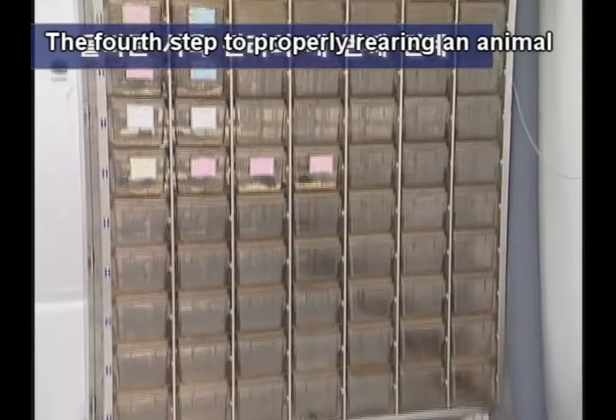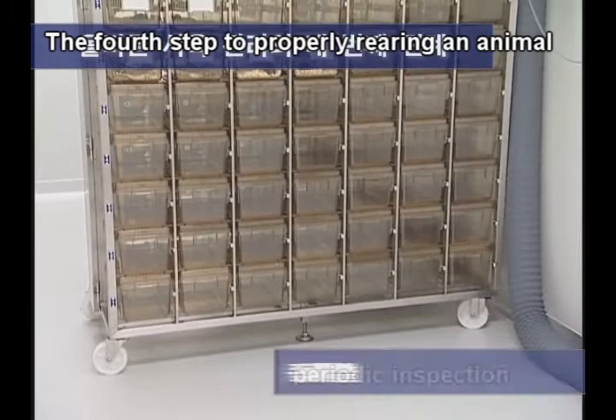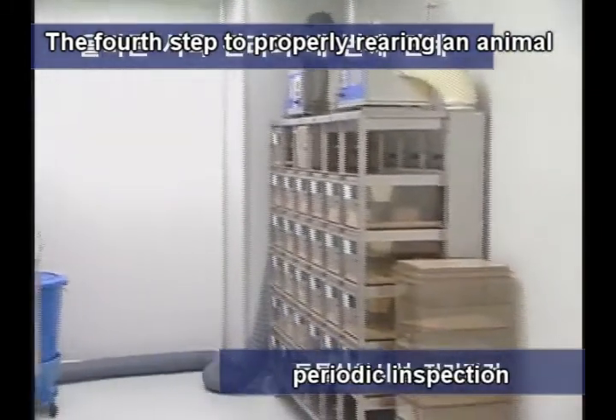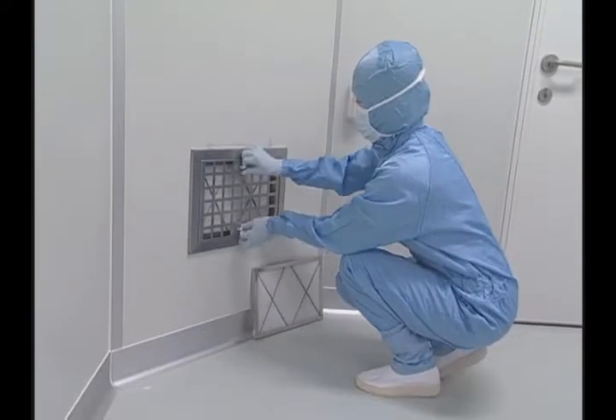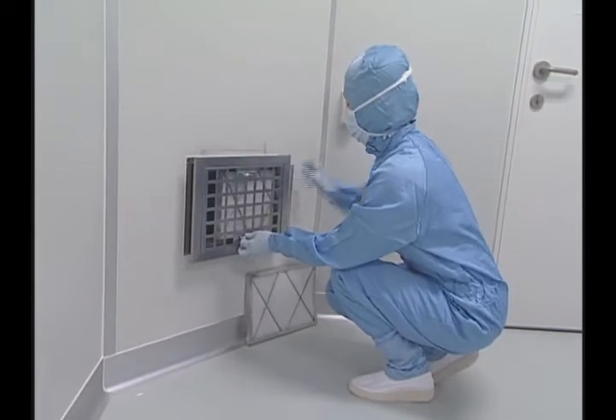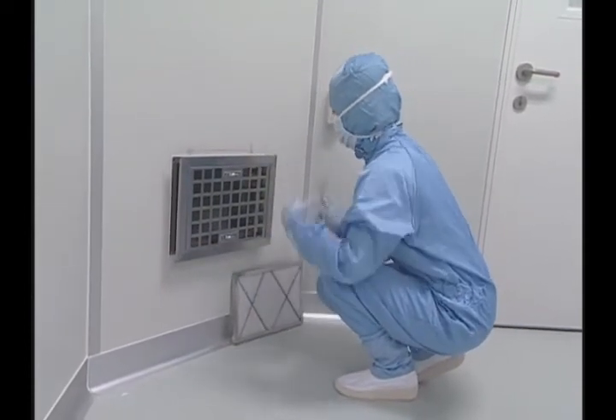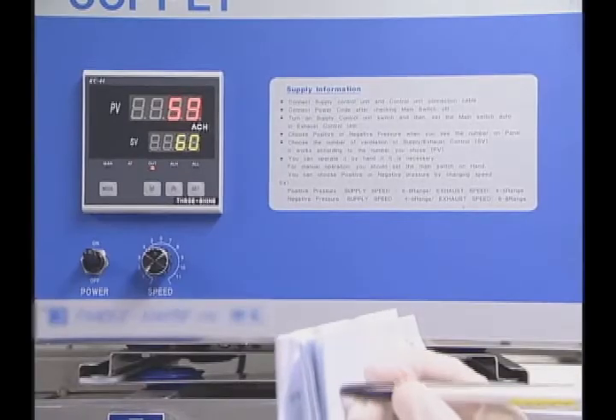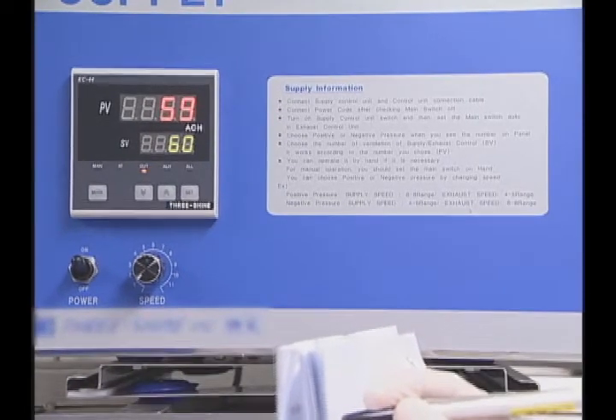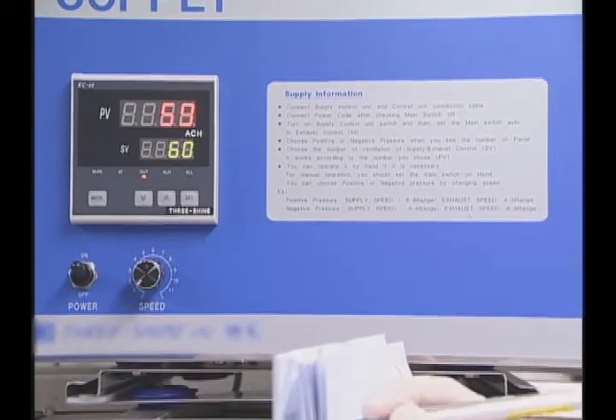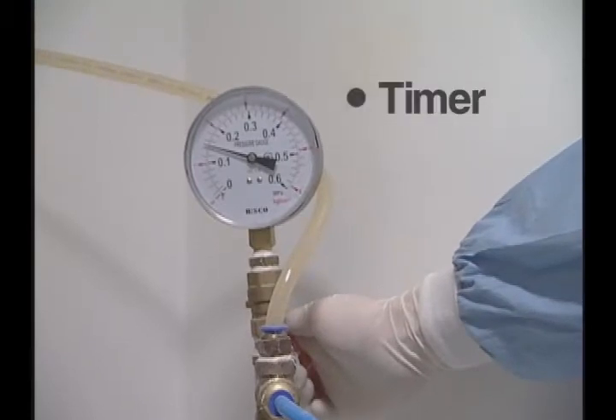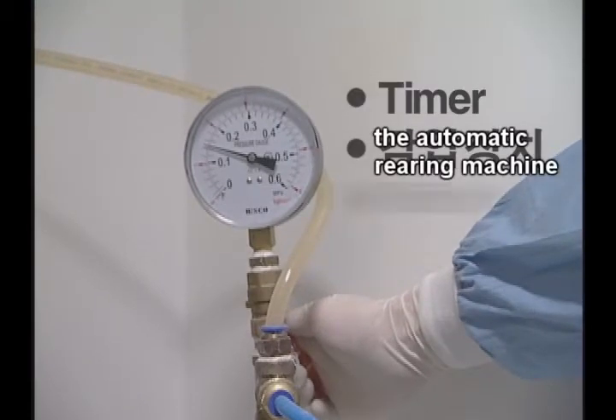The fourth step to properly rearing an animal is periodic inspection. The exhaust air duct pre-filters regularly need to be replaced, and the MVCS rack needs to go through periodic inspection too. When checking the automatic rearing machine, all of its parts should be checked thoroughly, including automatic feeding and washing systems, timers, filters, pipes, nozzles, and so on.